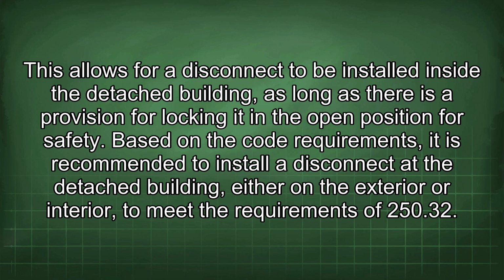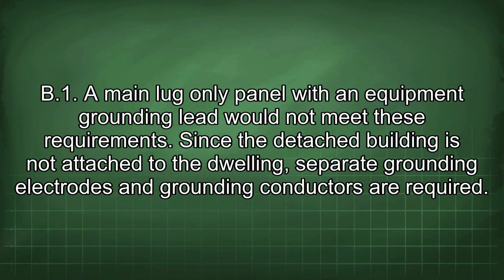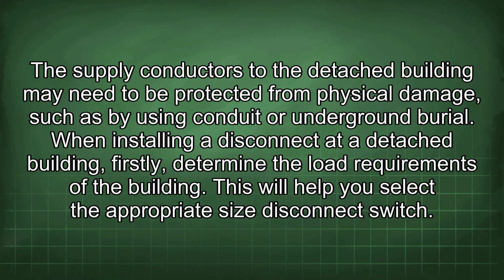Based on the code requirements, it is recommended to install a disconnect at the detached building, either on the exterior or interior, to meet the requirements of 250.32(B)(1). A main lug panel with an equipment grounding lead would not meet these requirements. Since the detached building is not attached to the dwelling, separate grounding electrodes and grounding conductors are required.